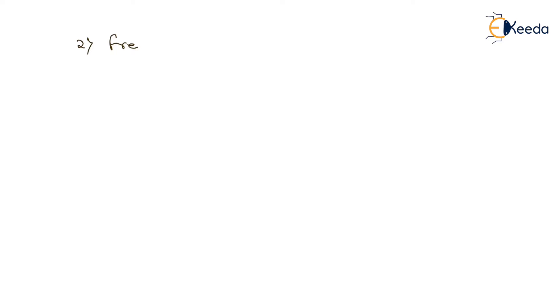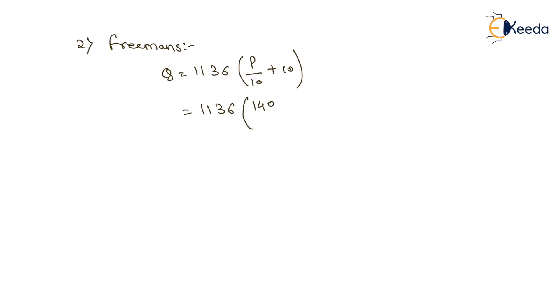The next will be the Freeman's formula. According to Freeman's formula, the discharge equals 1136 times (P/10 + 10). The value of P is 140. We divide this value by 60,000 to get the answer in meter cube per second, and we get 0.454 meter cube per second as the discharge from Freeman's formula.